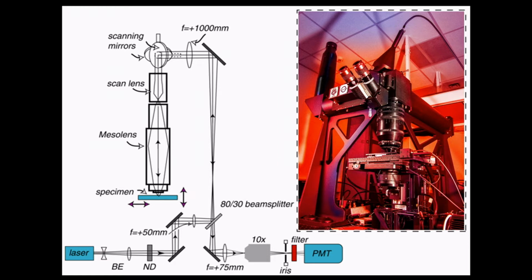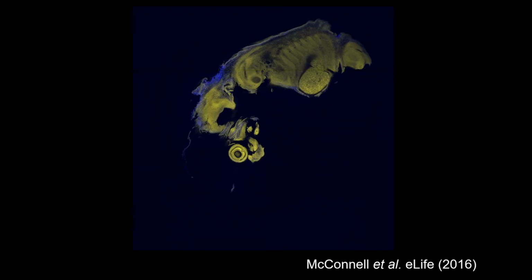So this is one of our Mesolenses here. This is the front optics here, with eyepieces obviously here. We have a liquid light guide that pipes in our cool LED illuminator, for wide field epifluorescence. What's not shown here is a camera, which normally sits at this port here, but I will describe that camera in a later slide.